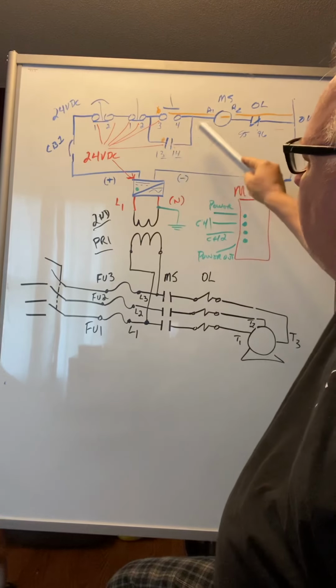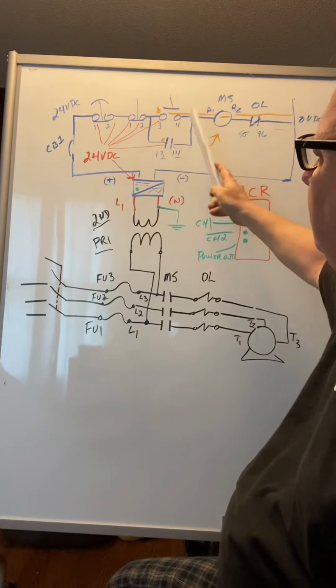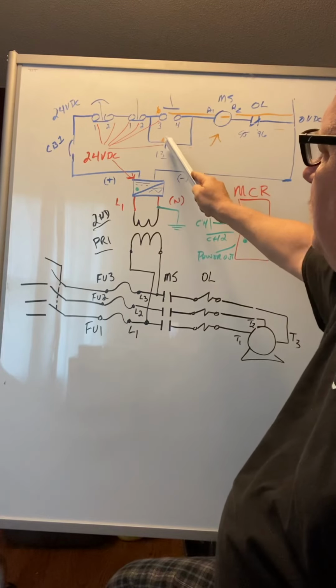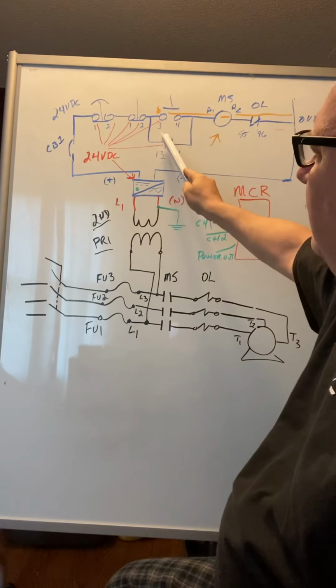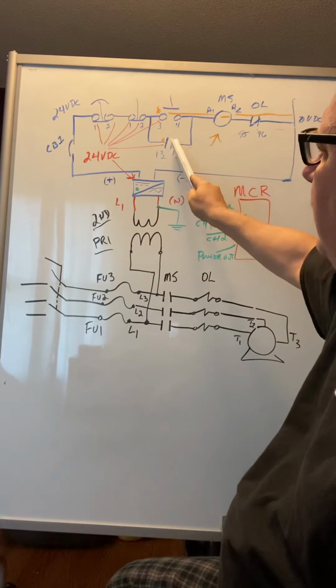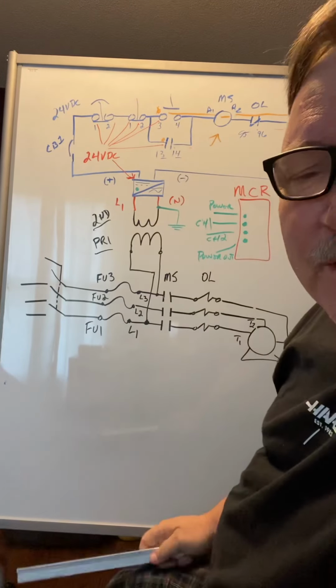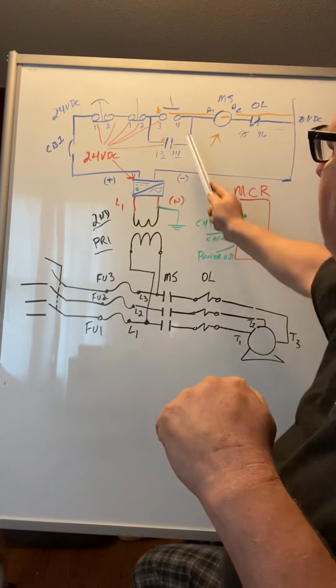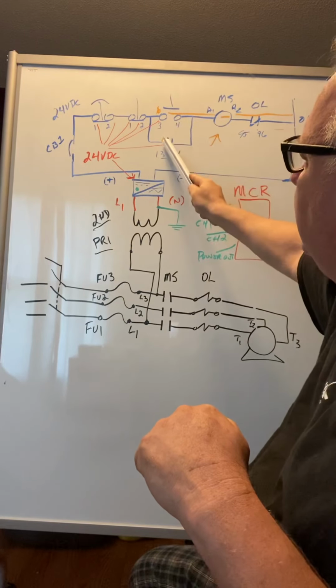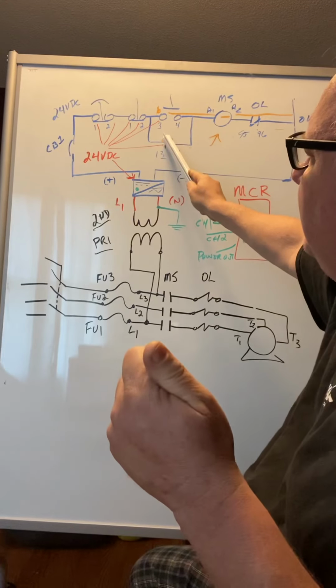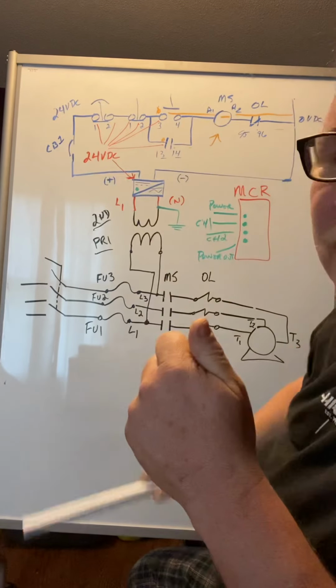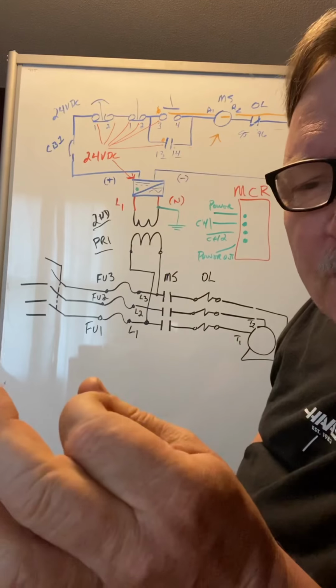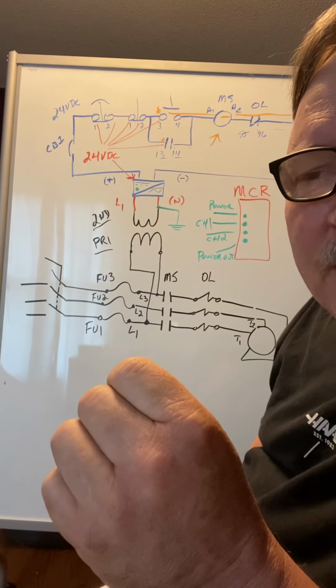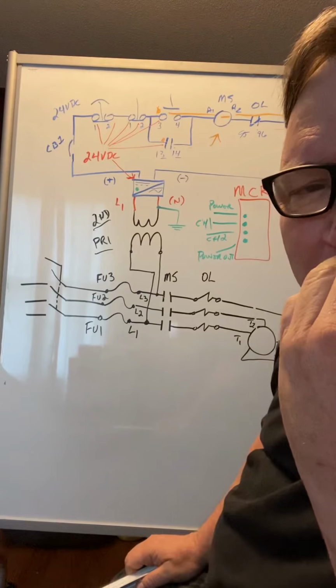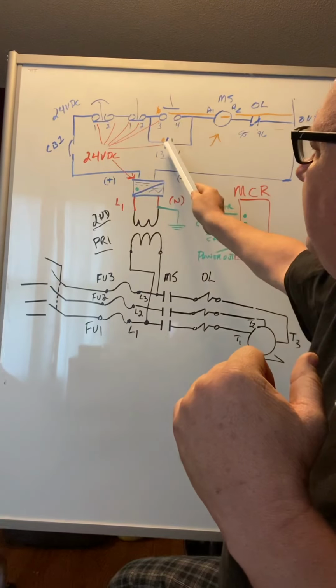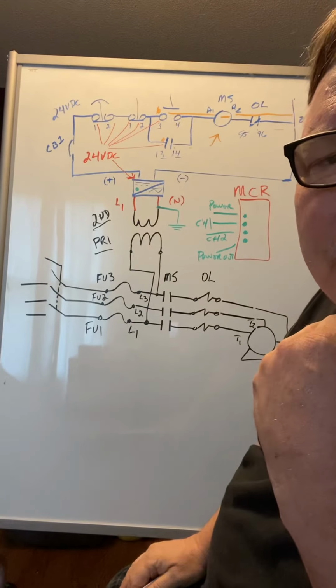because it's passing through. But now what you want to do is a voltage drop check across that with a meter. You're going to check your termination across here. This has to have 24 volts there for you to do this voltage drop check first. But when it's on, when your buddy pushes that, you're going to take your voltage DC, you're going to go across here to here. And if that is closed, you're going to see nothing. You should see nothing in your meter because the voltage is passing through. If it's not, then you're going to see 24 volts in your meter.